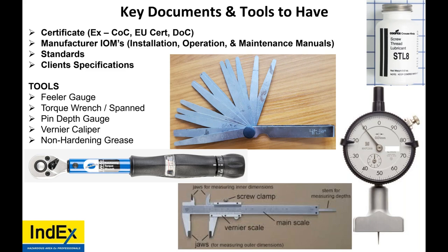Is there a difference between the longitudinal and parallel scratches of flange? Yes, absolutely. If the scratch goes across the flame path, that is the most dangerous, because then the gas can get out along that path. There are assumptions as to what percentage across is okay. Some people say 10%, some people say 20%. But how deep is that? Well, I would use the pin depth gauge.